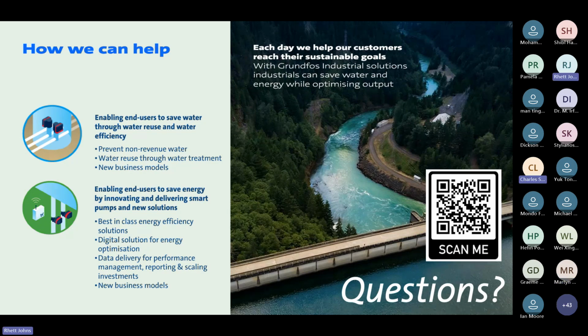Yes, absolutely. So in that sort of case, Martin, for a high flow system that's got variable flow, you would split up the flow requirements into multiple pumps, and then use a controller to switch those pumps on and off. As the flow demand increases, so does the number of pumps that you run in order to provide that flow throughout the system. And then the second one would be to use a system and a controller that is actually able to take input and change according to the requirements on the system.